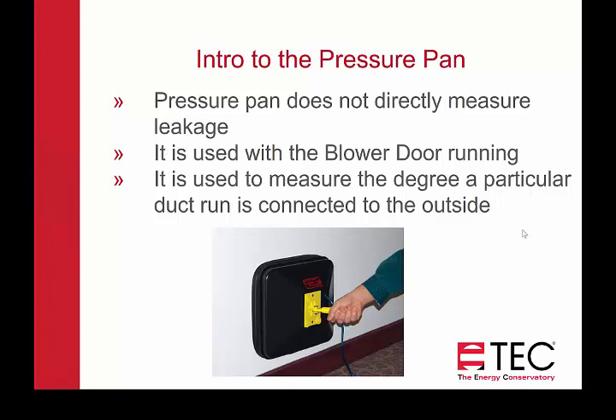On a recessed light, what you're essentially doing is measuring the pressure in the attic or something close to it. Recessed lights get even trickier because if that light has been on in the last few hours, you're going to have a much different temperature in there, and temperature definitely affects pressure. So that will affect your reading also, making it difficult to use a pressure pan on that application.